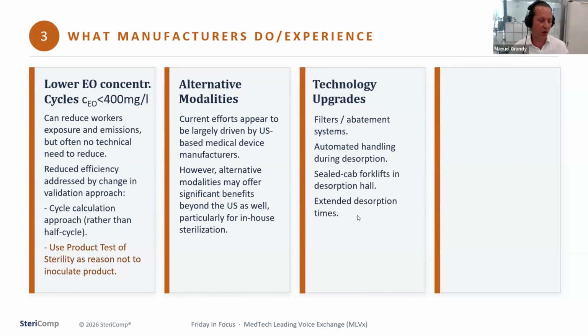So it's very interesting. So instead of, after 3 days, you would often be under the limits for the patient. For example, 4 milligram ethylene oxide per device is a limit, and you would drop under this limit after 3 days after EO sterilization, and then you could release it to the market. But still, there is EO on the pallets and so on, and of course also in the product. So some companies say, well, I want to have it 7 days in your desorption, in your control desorption. And this helps a lot then downstream also in the warehouses, or 14 days, okay, extended desorption times.